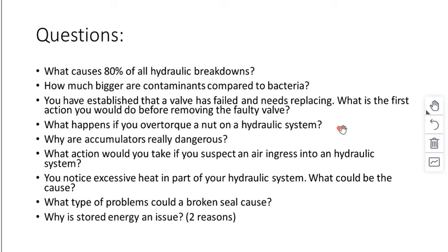Next question. What happens if you over-torque a nut on a hydraulic system? Right. All nuts and bolts in a hydraulic system are torqued up with a torque wrench. If you over-torque them, it can potentially destroy the seals, and it can be counterproductive. So instead of sealing it better, you're actually sealing it worse. And you might have little gaps where the hydraulic oil can seep out. Other than that, you might strip the thread of your nuts and bolts, and then obviously they won't work at all.